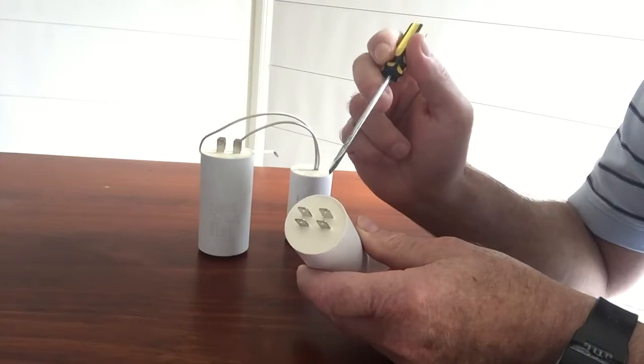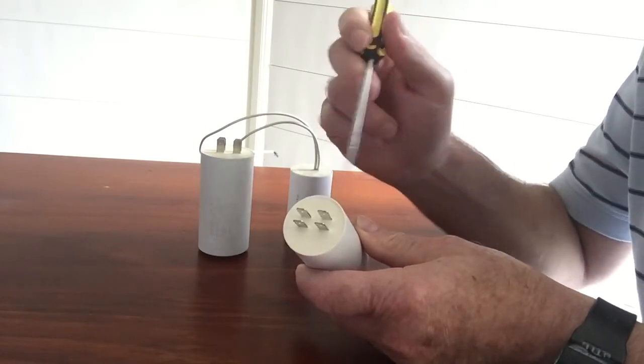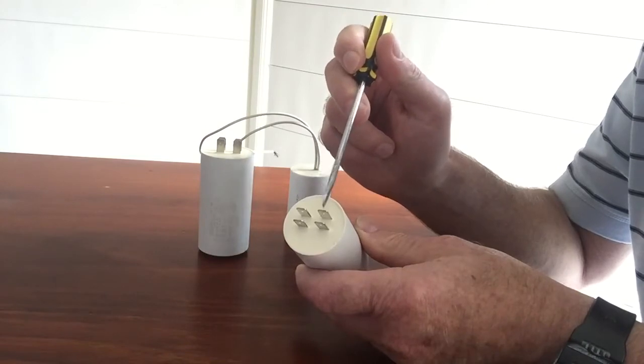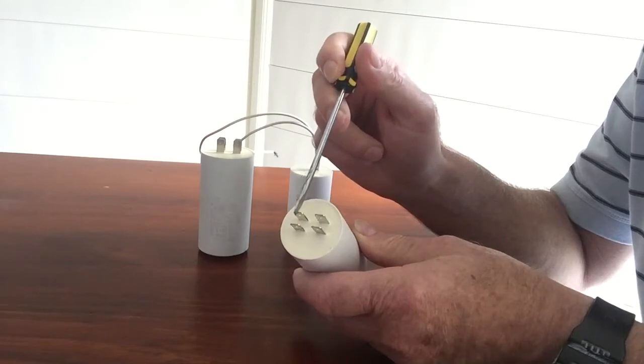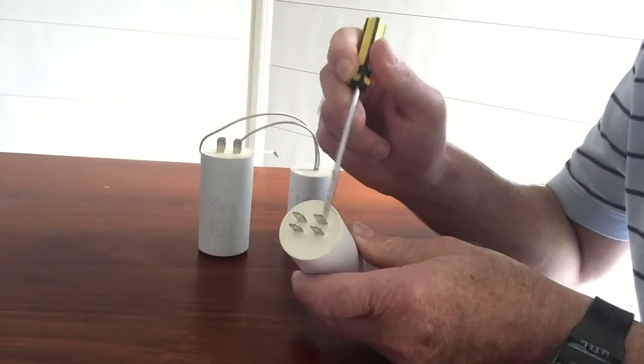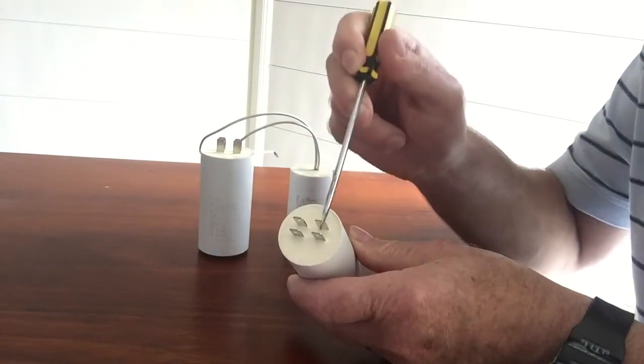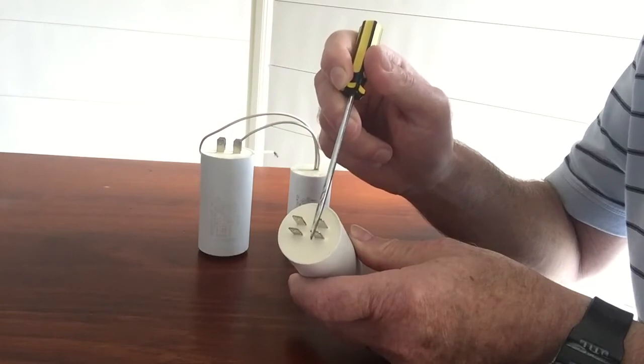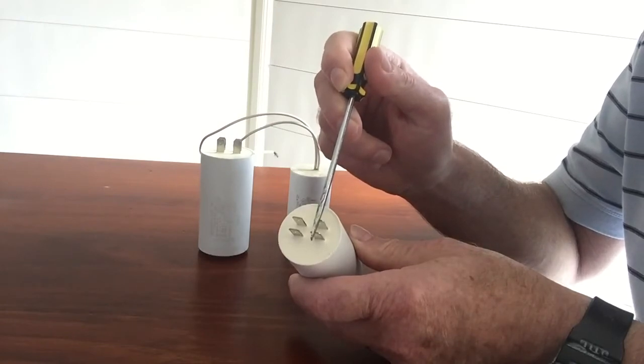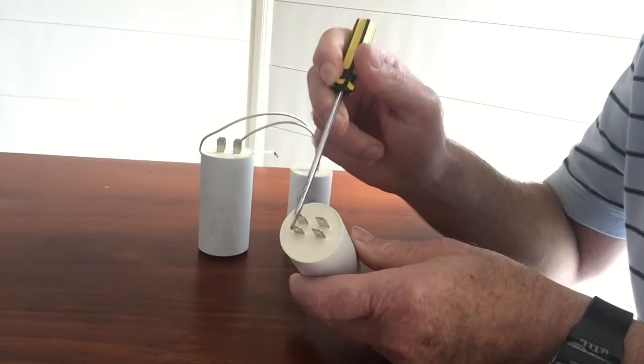So if you've only got two wires going to your capacitor, it doesn't matter which way they go. You can put one wire on here and one wire on there - it doesn't matter as long as they go across. You cannot put two wires on those two terminals because they're the same terminal. That means it won't be going across the capacitor. So put one on either one of those and one wire on either one of those.